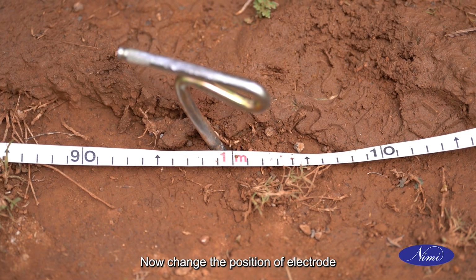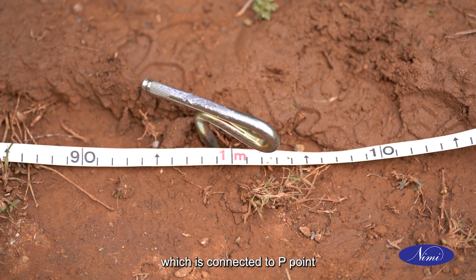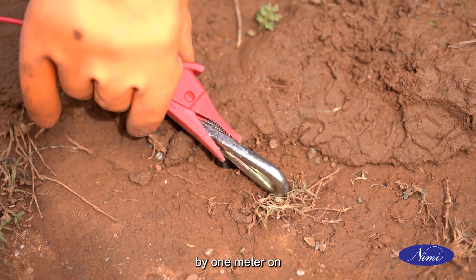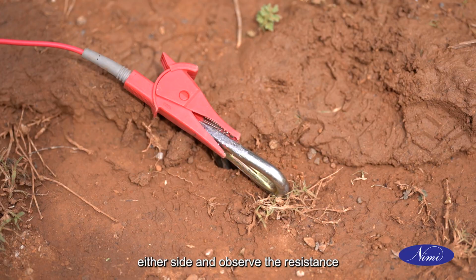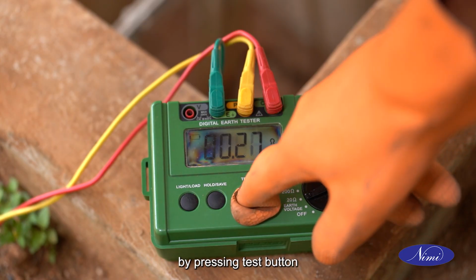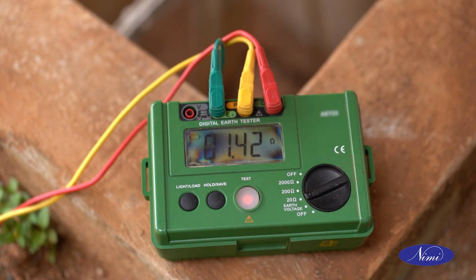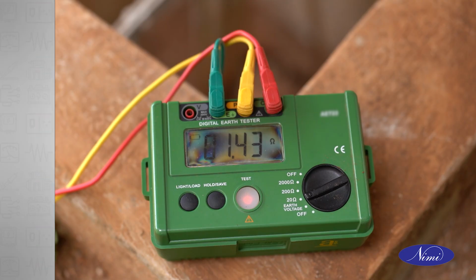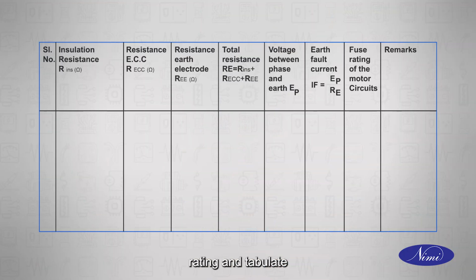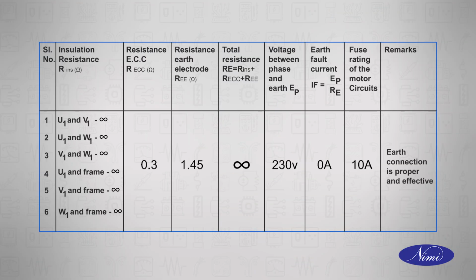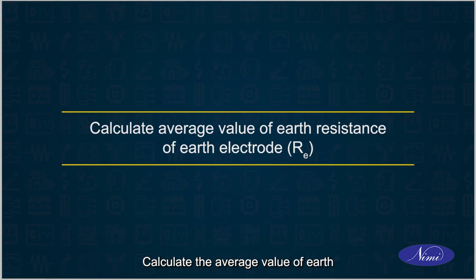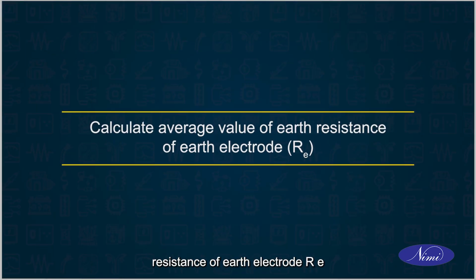Now change the position of electrode which is connected to P point by 1 meter on either side and observe the resistance by pressing test button. Note down the resistance reading and tabulate. Calculate the average value of earth resistance of earth electrode RE.